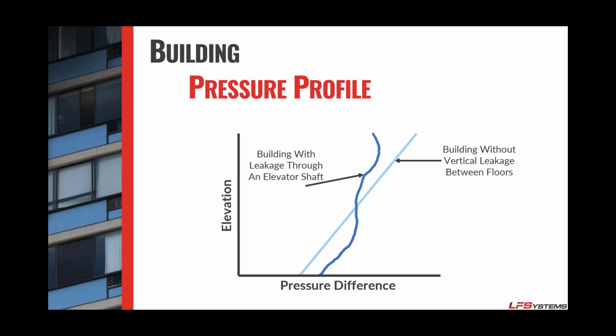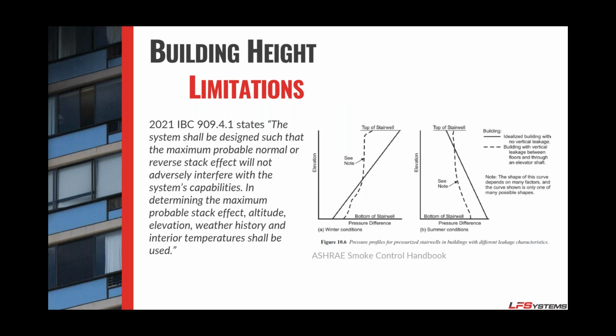A typical building pressure profile looks something like this. The light blue line that you see here would be if there's no leakage between the floors, okay? You'd have the natural lift of the building. However, if there is leakage between the floors, it would look a little more like this squiggly line here. And one thing to consider, IBC 909 mentions this, is that your building actually flips from summer to winter. In the winter, the lowest pressure point is going to be the base of the building, whereas in the summertime, it's going to be toward the top of the building. So, trying to balance a pressurization system for all conditions.